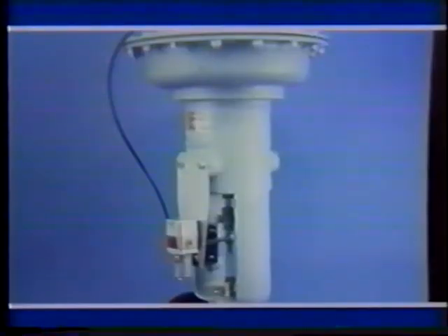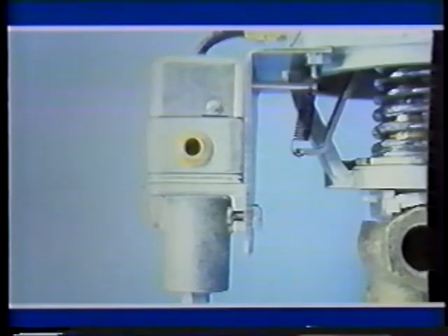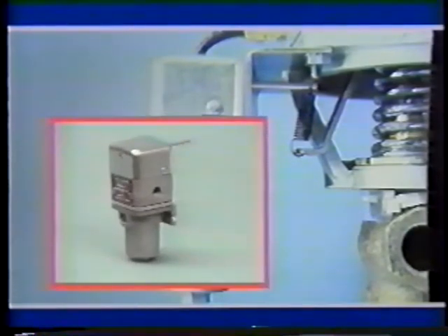The 10, 30, and 80 square inch actuators will support the addition of a positive positioner. This positive positioner provides the same effects as the damper actuator previously discussed, the ability to positively position the valve stem in relation to a given signal.